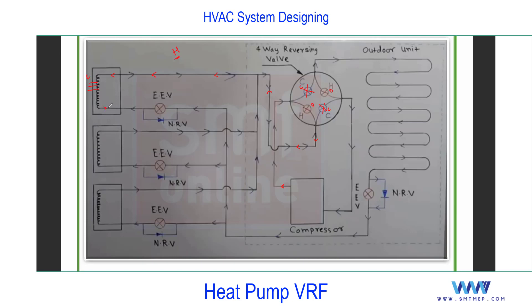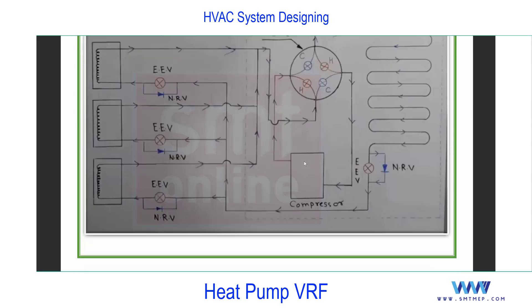After condensing in the indoor unit, the refrigerant in liquid form does not pass through the indoor electronic expansion valve - that EEV is closed in heating mode. Instead it flows through the bypass line via the NRV. It then enters the outdoor electronic expansion valve, where it loses pressure and temperature, and the outdoor unit now becomes the evaporator. This completes the heating mode cycle. Next we have the more advanced type of VRF - the heat recovery type.